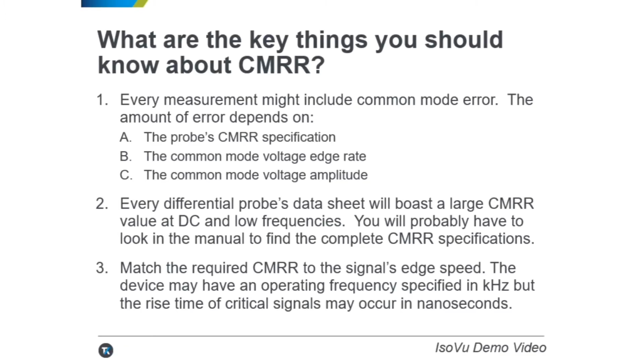So what are the key things you should understand about common mode rejection ratio? First, every measurement might include common mode error, and the amount depends on the probe's CMRR specification, the common mode voltage edge rate, and the common mode voltage amplitude. Second, every differential probe's datasheet will boast a large CMRR value at DC and low frequencies, but you'll probably have to look in the manual to find the complete CMRR specification. Third, match the required CMRR to the signal's edge speed. The device may have an operating frequency specified in kilohertz, but the rise time of critical signals may occur in nanoseconds.